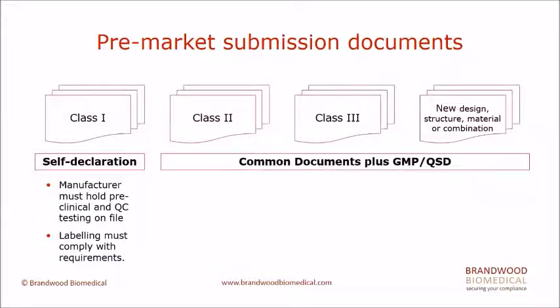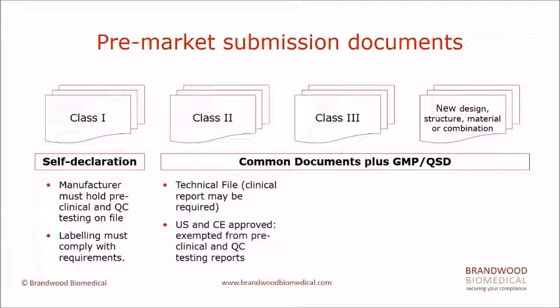For Class 2, 3, and the novel device, the common documents plus the GMP and QSD certifications are required. For Class 2, the technical file and clinical evidence report are not part of the initial submission, but they may be required for review during the reviewing process. For Class 2 devices, if you have the US and Europe approval, you can be exempted from providing preclinical and QC testing reports. And again, they may be requested during the reviewing process.